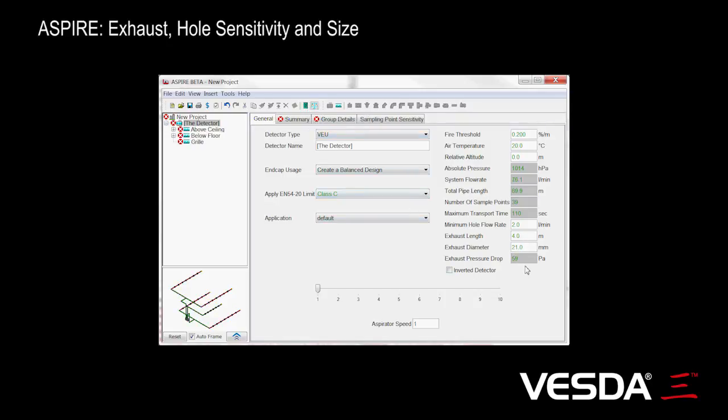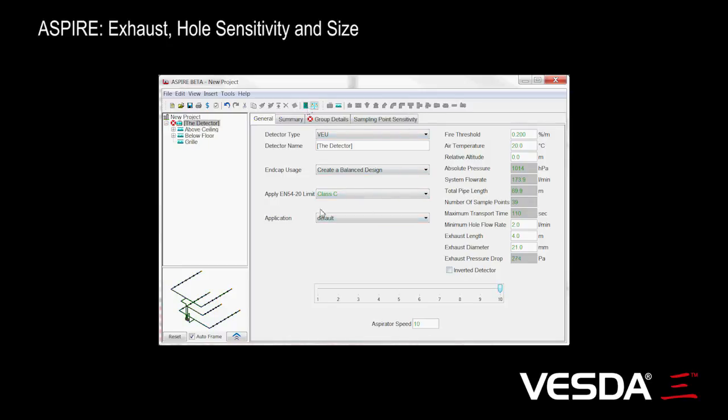We'll get 59 Pascal. But if we increase to maximum speed for our detector and run the same calculation again, you see we're getting a 274 Pascal pressure drop.